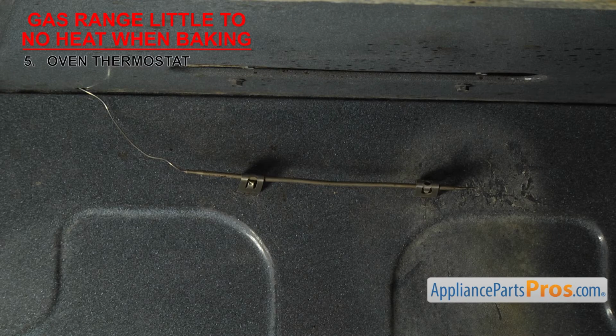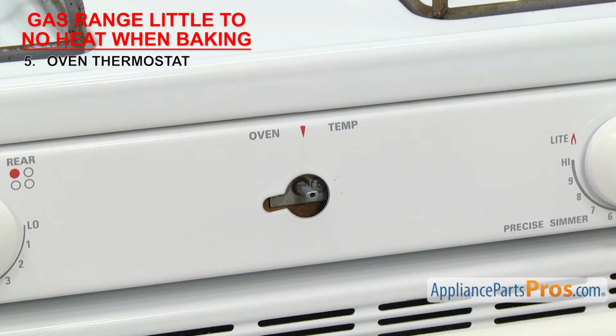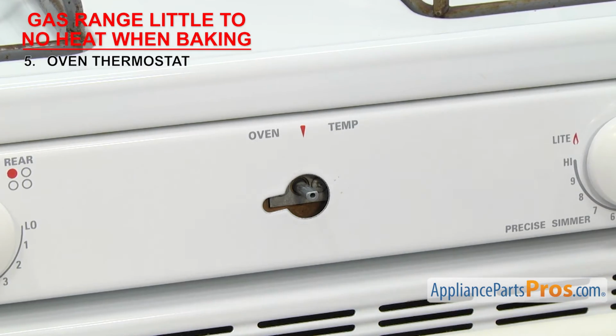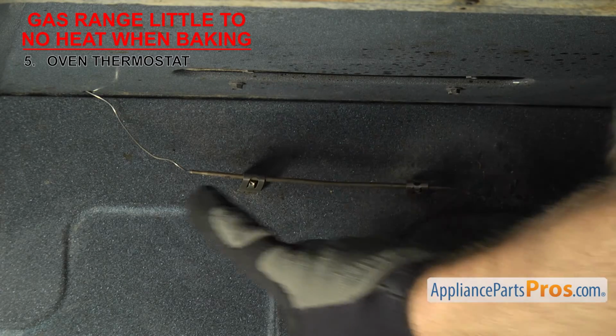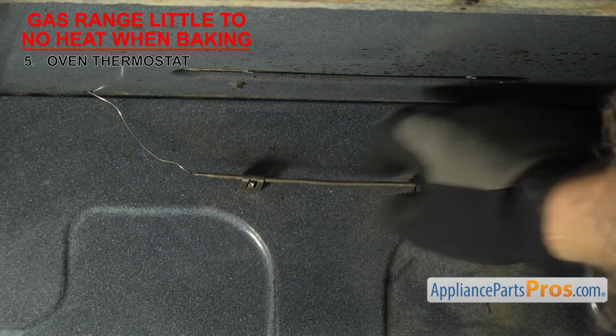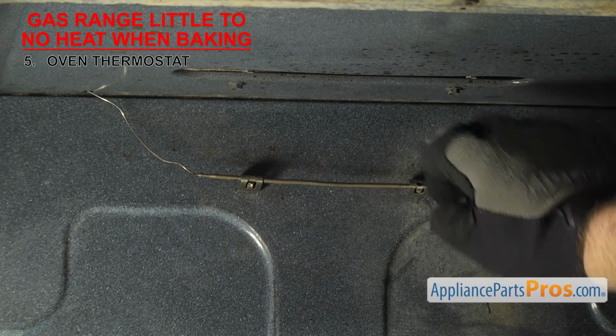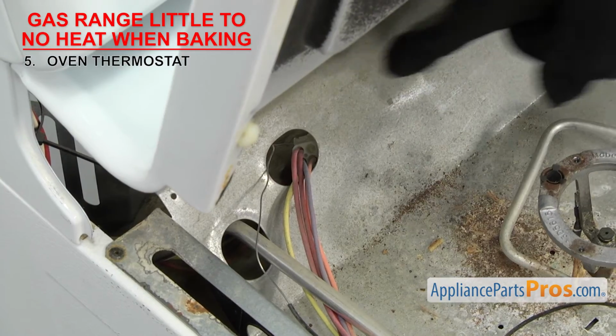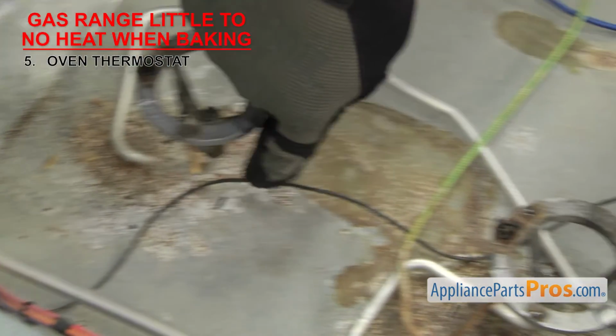The sensor bulb has fluid in it that expands through the capillary tube to the switch body. If the thermostat has gone bad, your gas range could have little to no heat when baking. First, look at the bulb. It should be mounted in the corner of the oven on its mounting brackets and not hanging down. Then inspect the bulb and capillary all the way up to the switch body to make sure it's not leaking, kinked, or damaged in any way.